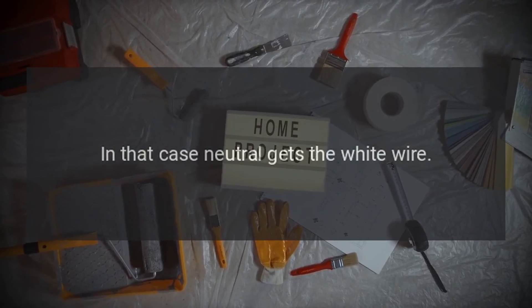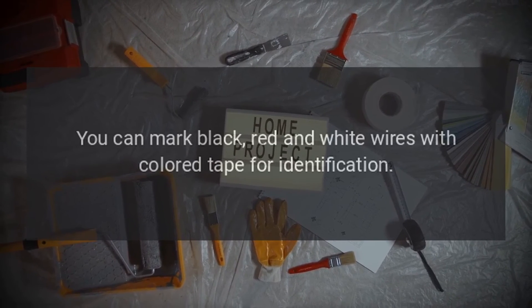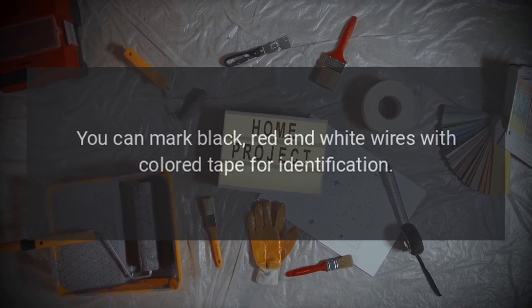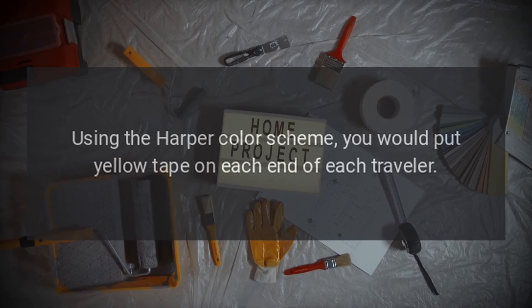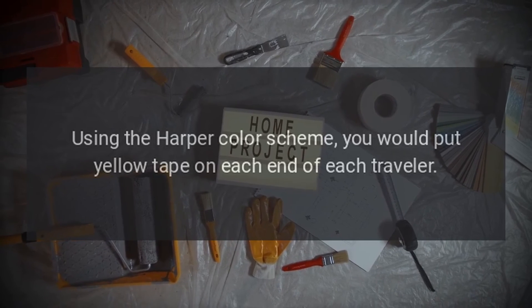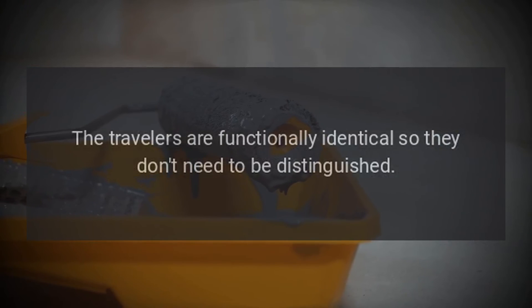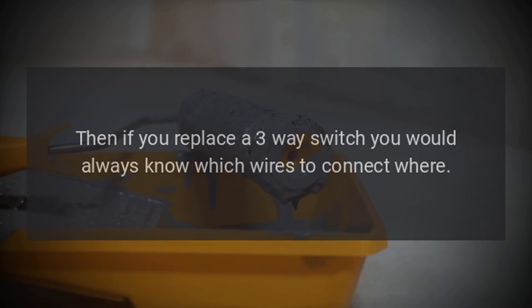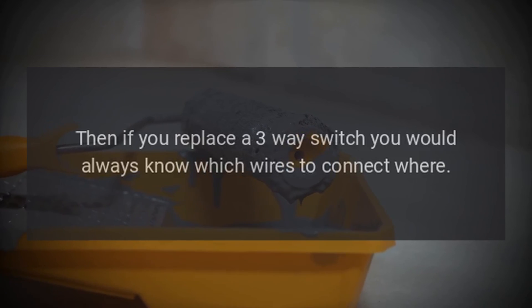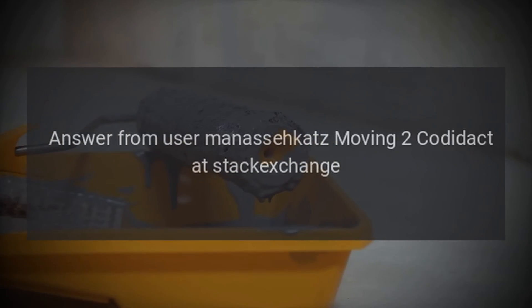In that case, neutral gets the white wire. You can mark black, red, and white wires with colored tape for identification. Using the Harper color scheme, you would put yellow tape on each end of each traveler. The travelers are functionally identical so they don't need to be distinguished from each other. Then if you replace a three-way switch, you would always know which wires to connect where. Answer from user manassehkatz, moving to Codidact, at Stack Exchange.